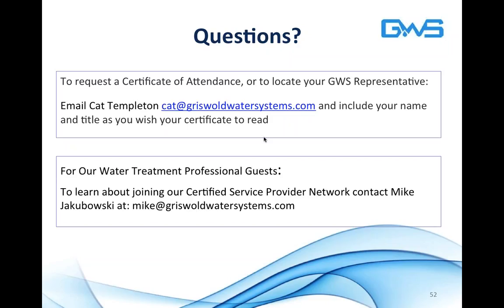Those are two very good and very specific questions. The answer to both is yes. For the first, we utilize biocoupons, and we're developing our own process and basic standard for that, absent any guidance in the literature, ASTM, or standard methods. There's total silence on testing or monitoring for biofilm in building water systems, whether potable or cooling water, so we're actively engaged in setting that up.